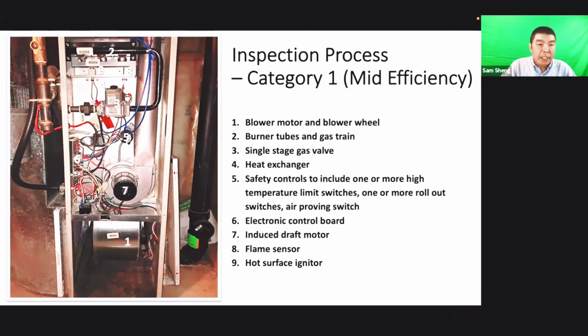If you see a hot surface igniter, you should check it, because it's normally a silicone material. When it has been running a long time, you can see some white stuff on the outside of the igniter, which may be burned, degraded material.